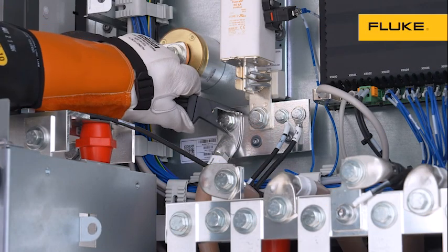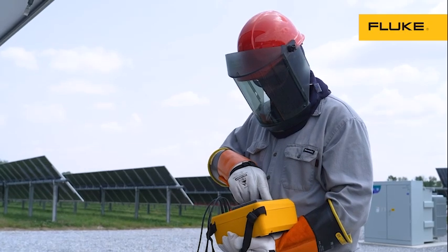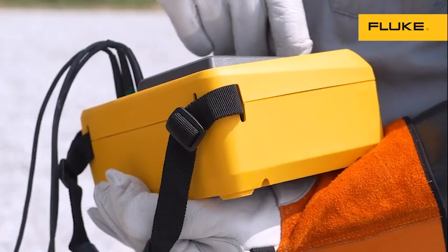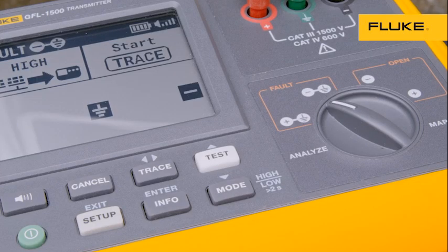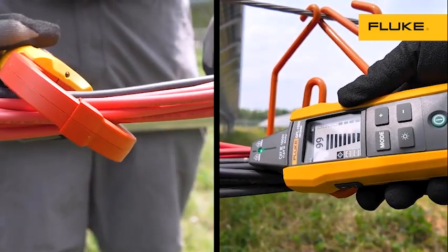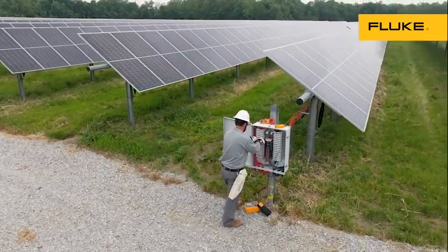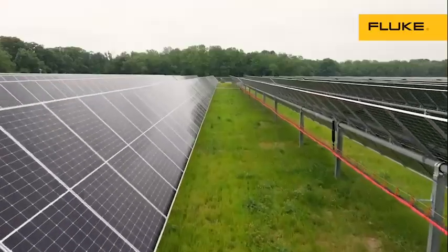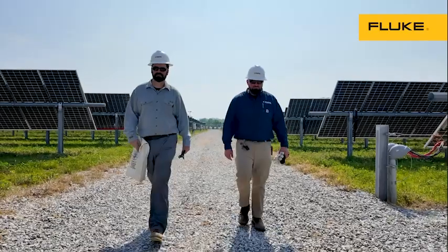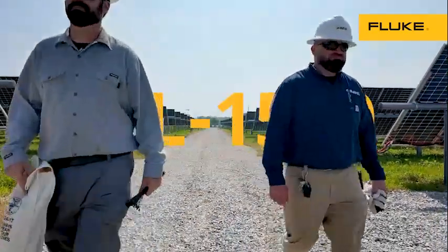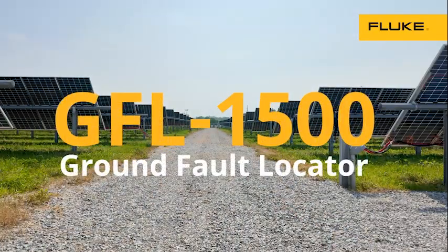Start at an inverter or combiner box with the GFL-1500 transmitter. The transmitter will generate a traceable signal through the fault path, so you can then grab the signal tracing clamp or receiver to follow the signal and pinpoint the fault in your array. With fault track technology, the work that used to be a challenge is easier than ever.